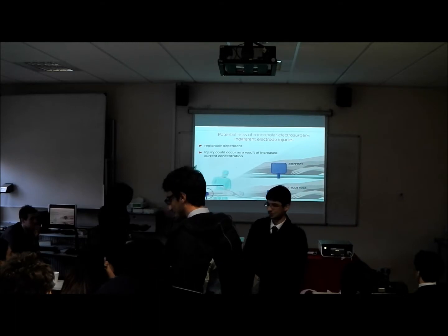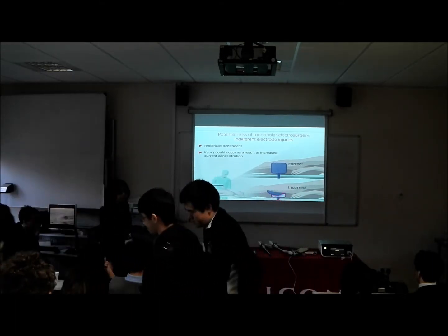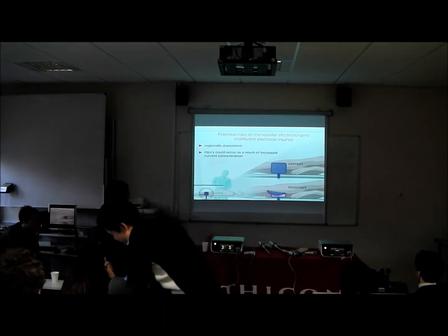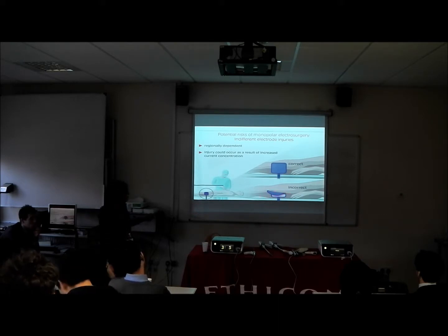And if you can see here, this return electrode hasn't been properly applied, and therefore what will happen here is the density of the current will increase here and the patient can get burns here. So what we have to be careful is that the patient return electrode is properly applied.